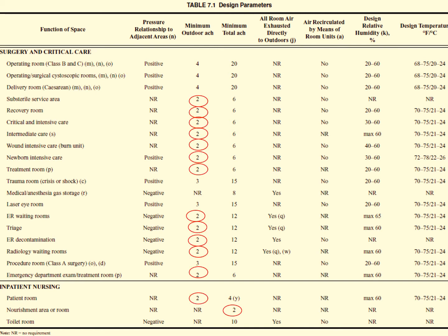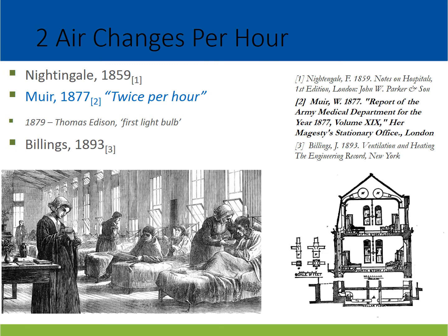So let me tell you a story about one of these numbers. If you've ever used this table, you've used this number, 2 air changes per hour. That's the most common number in the table, our outside air ventilation number, and we use it for most spaces. I tracked this number through history. It was in the code in the 70s, in the 60s, I found it in the 40s, the 20s, the 1910s, I kept going back, and finally the earliest reference I found is from the 1870s. So I've come to call 2 air changes per hour our horse and buggy number.